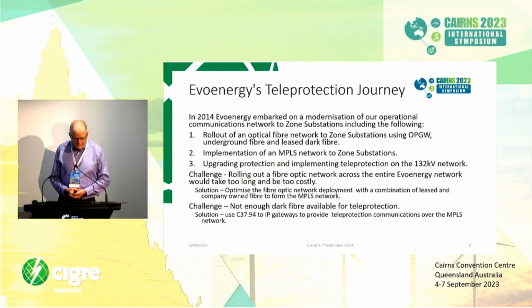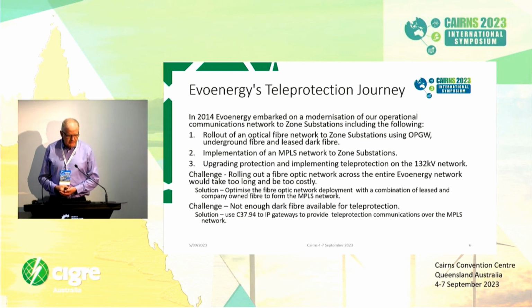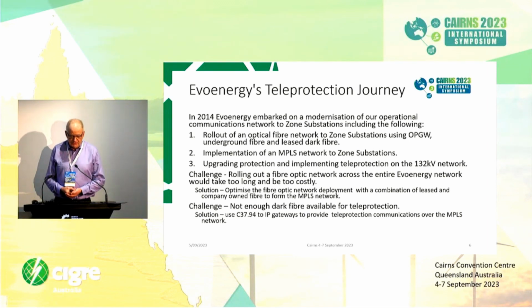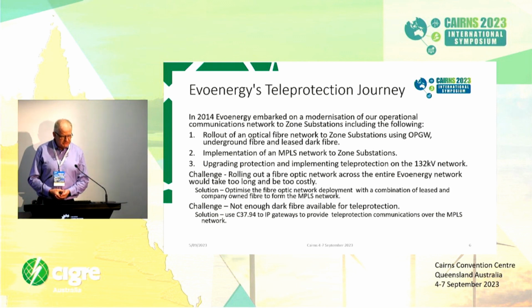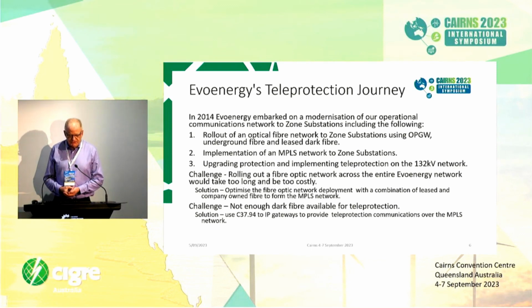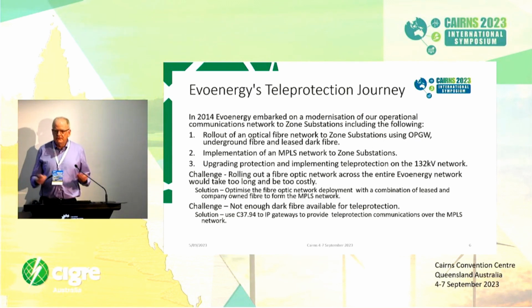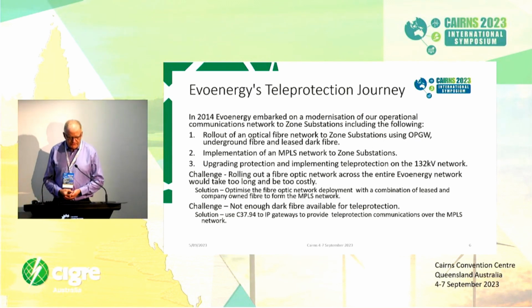And I guess that comes with two challenges. One was, like I said, just rolling out the optical fibre network took too long, so we needed to get this thing up and running pretty quickly to meet those protection fault clearance times. And the second challenge was not having enough dark fibre for teleprotection. So, having the MPLS network, we needed to find a solution to put the teleprotection using C37.94 over the IP network.